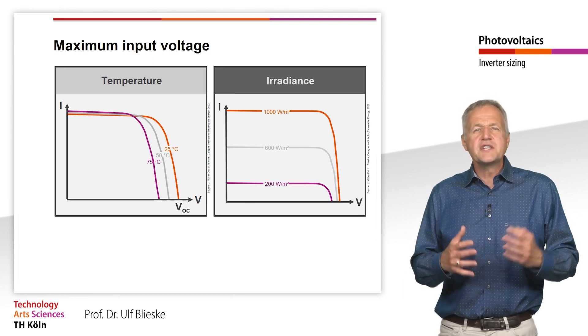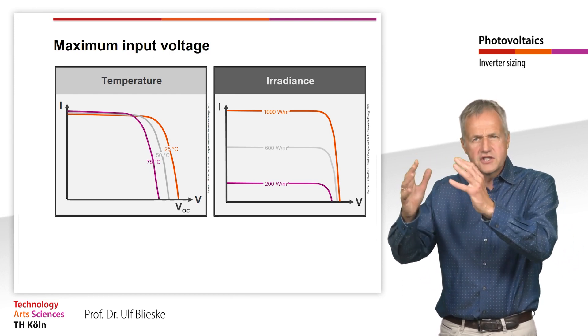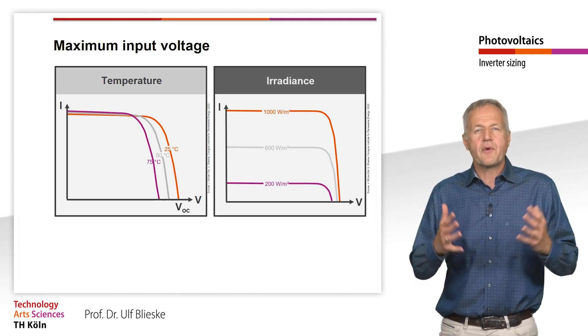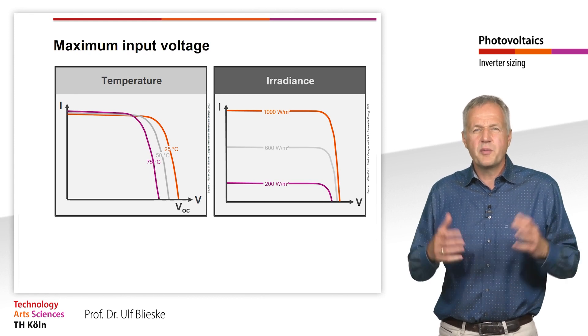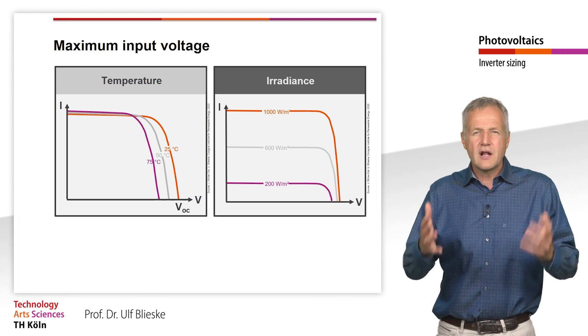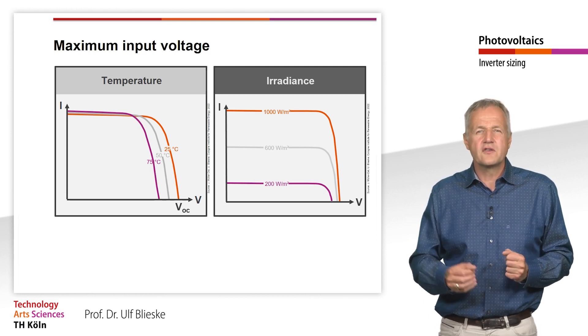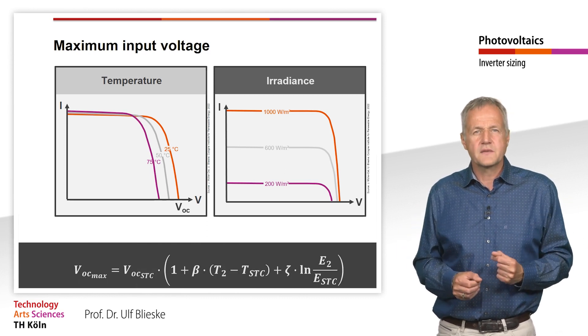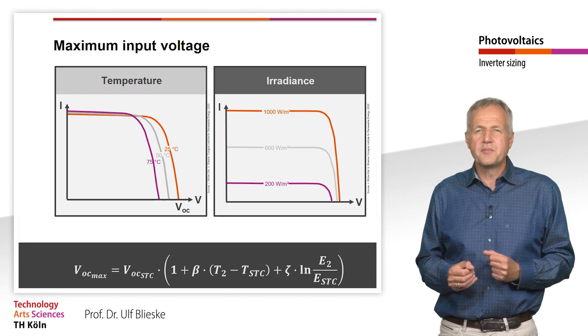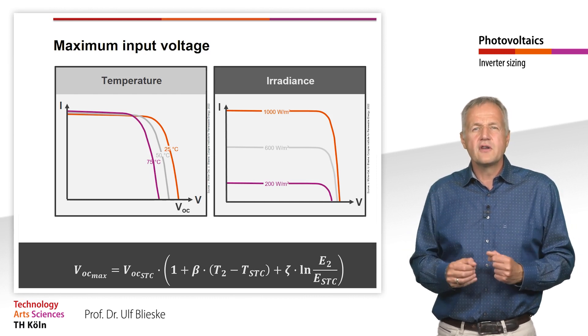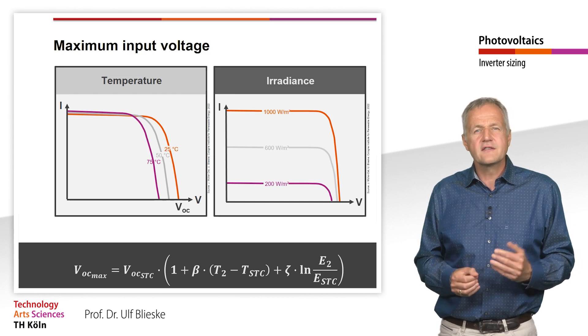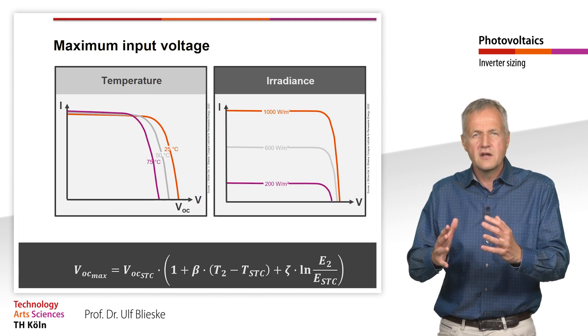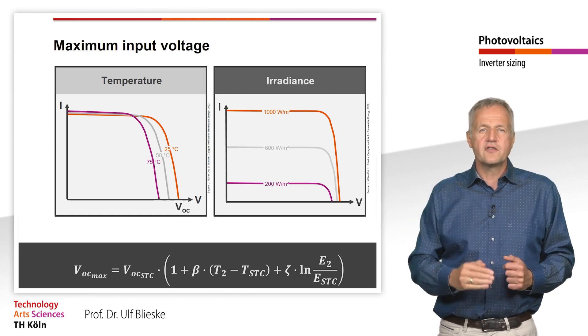The solar generator therefore reaches the maximum open circuit voltage during a power failure on a very cold, very sunny day around midday. The inverter must be prepared for this extreme case. To calculate the highest possible open circuit voltage we can use the equation which we have already learned in this context. But what is the coldest temperature and can the solar module even get the maximum irradiance at these extremely low temperatures?